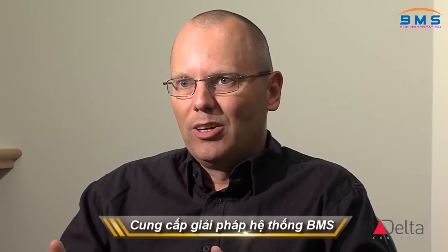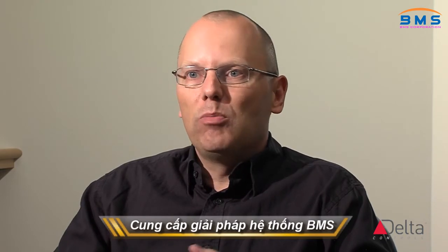When you take over that exhaust fan, the only custom programming you need to do is for that exhaust fan. If the VAV is running the configurable algorithm, you don't need to do any extra work for that. You're just adding extra for the unused I/O points you want to repurpose.